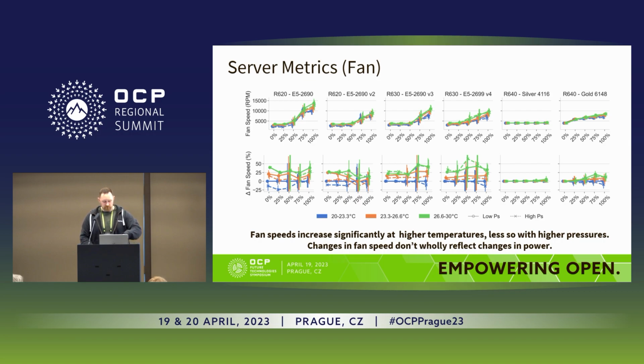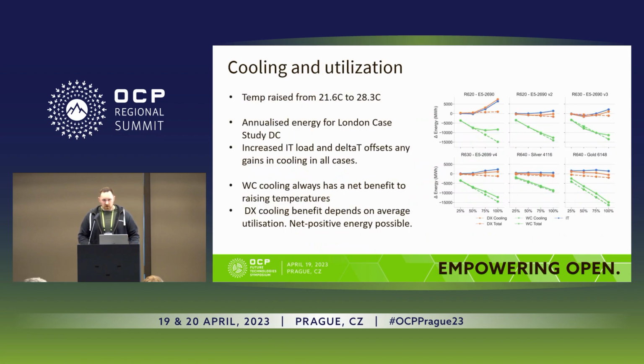What you're seeing here on, by the way, the blue, and I know there's a lot of graphs on this. I like data visualization, so I apologize for the pictures. But what we're looking at here is the impact on fans. What we're seeing is there's very little impact on CPU temperature raising, quite a lot on fans. So what we've done is we identify what the IT does now. So first part of the puzzle, identify what temperature does to IT, cross-generationally, on a configuration level. Now let's look at what actually happens from a cooling point of view.